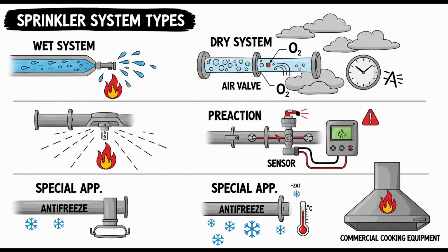We're going to see how something as simple as a tiny hole in a valve clapper can be a critical piece of design, or why a sprinkler head in a freezer might need a detector activating before it does. It's fascinating stuff. Right, let's unpack this, starting, as you said, with the most common system, just as a point of comparison. Right, the wet pipe system. It's the standard. You see it everywhere. The default, basically.